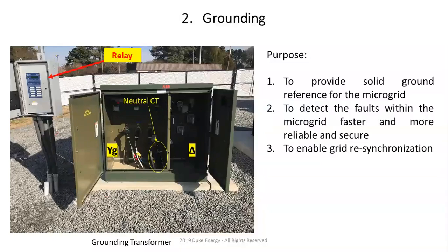So how do you do that? Pretty much in your microgrid controller, you just put in: when the PCC is closed, this is open, or the breaker you use to energize this transformer is open. The moment you go into island, you open the PCC, then you close the grounding transformer, right? Now, when you go back to the grid, you have to hold this grounding transformer closed until you resync back up to the grid and close your PCC. And then you open it up. That's probably about 28 milliseconds after you close your PCC.